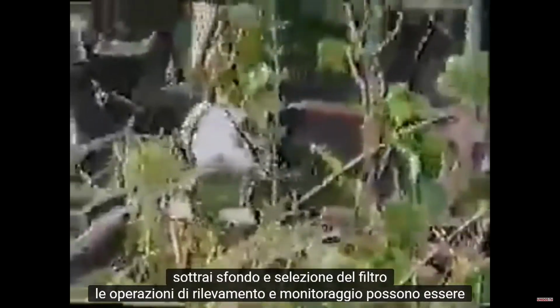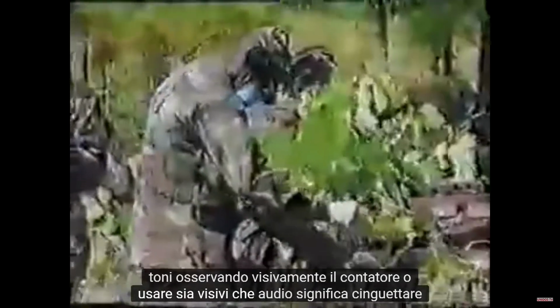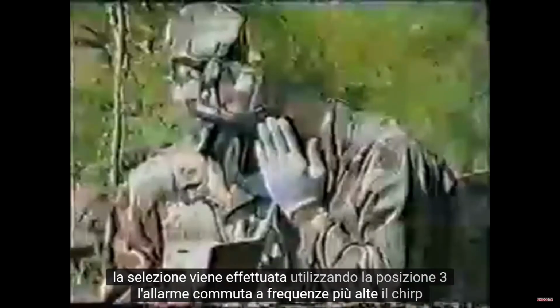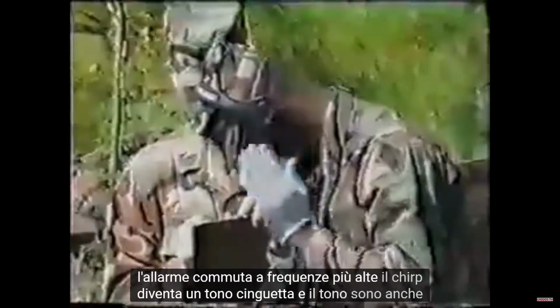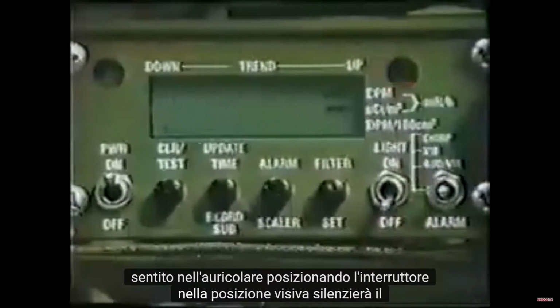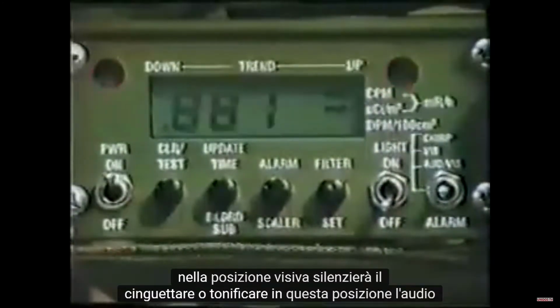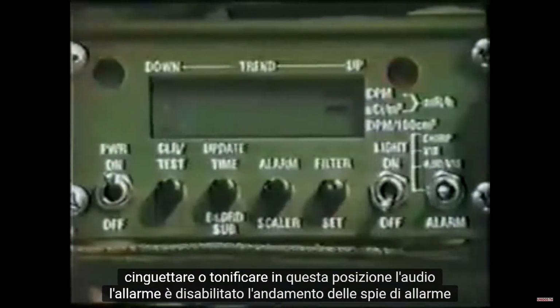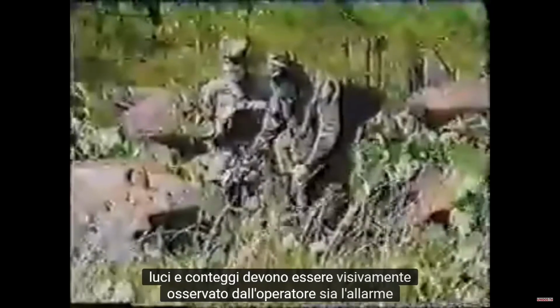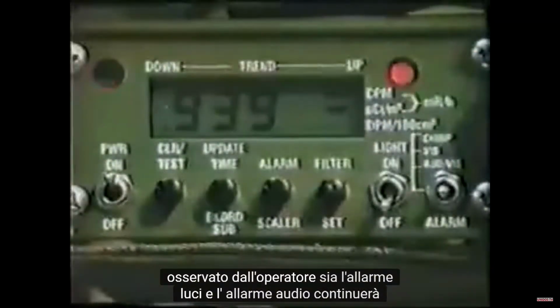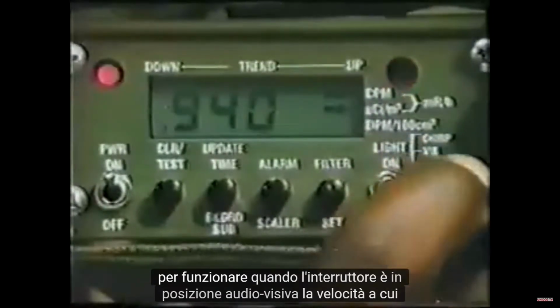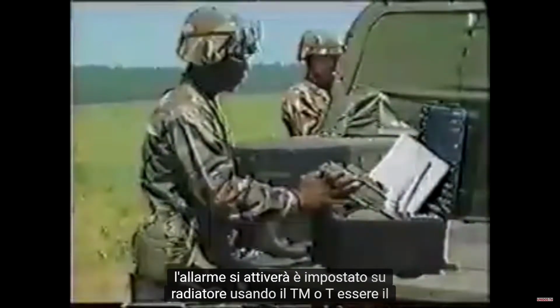Survey and monitoring operations can be performed by listening for chirps and tones, by visually observing the meter, or using both visual and audio means. Chirp selection is made using the 3-position alarm toggle. At higher rates, the chirp becomes a tone. Chirps and tone are also heard in the headset. Placing the switch in the visual position will silence the chirp or tone. In this position, the audio alarm is disabled. The alarm lights, trend lights and count rates must be visually observed by the operator. Both the alarm lights and the audio alarm will continue to function when the switch is in the audio-visual position. The rate at which the alarm will activate is set into the Radiac meter using the TM or TB.